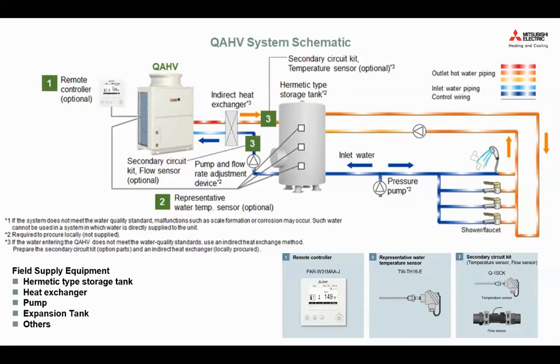And then on the right-hand side of the heat exchanger, let's say you have 10 degrees C of city water mixing with the water from inside the storage tank. So it may be 10 degrees C going into the indirect heat exchanger, and then you can have 65 degrees C coming out of the exchanger into your tank. And then from the tank, you may be applying 60 or 65 degrees C, and then mix that with the inlet water from the city to create maybe, let's say, 45, 50, 55 degrees of hot water, depending on your local jurisdiction, and then deliver hot water for, let's say, shower or faucet for domestic hot water usage.